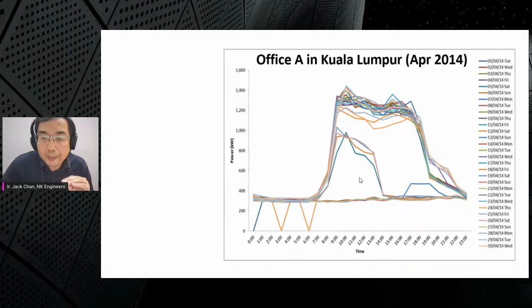We log the daily profile, and from it you'll be able to know where your various loads are. If you find a constant load, no matter whether it's morning, afternoon, or evening, that's called the base load. In this building, for example, the base load is about 300 kilowatts - no matter what time of day, this base load will always be there. It's the fundamental load required for the building to operate even with no occupancy.